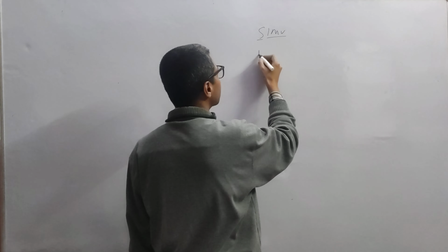It synchronizes the patient's own breath into mandatory breath. That's what we call synchronized. And it is giving mandatory ventilation intermittently, so we call it intermittent mandatory ventilation. Here also there are 2 types. You can control volume or you can control pressure. You have to control one thing, either volume or pressure.